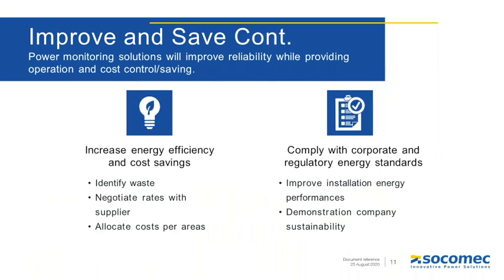The last two goals of power monitoring are: number 4, you can identify the loads in your installation that require high energy, and take appropriate actions to limit the peak demand by scheduling delays between loads, so you won't be starting all the motors at the same time.